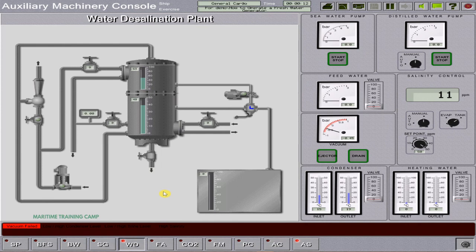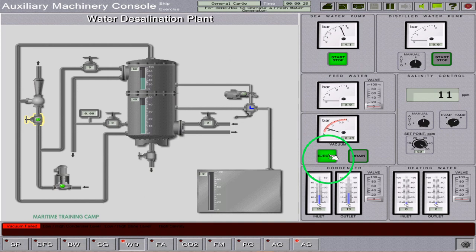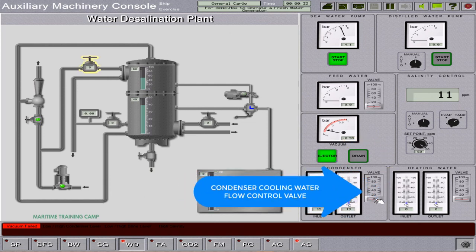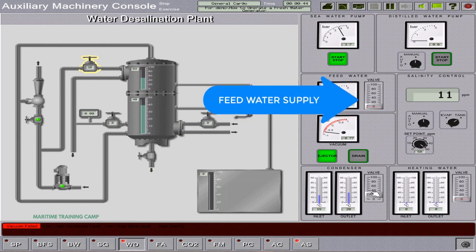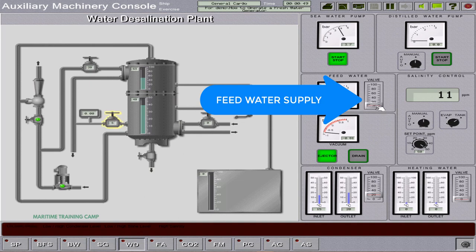To put the freshwater generator in operation, we switch on the seawater pump. Then we open the ejector cut-off valve. Next, open the condenser cooling water supply valve — we open it at around 20%. Then we open the feed water supply as appropriate to the plant capacity; in this case, we open it at around 20%.